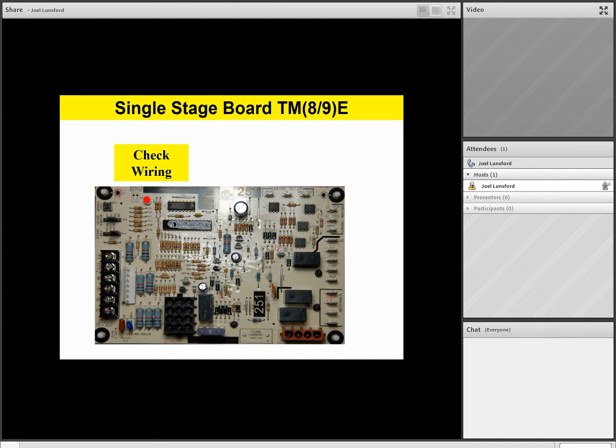In addition, did someone forget a jumper? As we said a few minutes ago, a technician sometimes will use jumpers for diagnostic purposes, which is okay, but we want to make sure that they don't leave the jumper on there, because what will happen, it will throw this flash code when you go into the heating mode again, because it'll think it's a stuck switch. So if no one forgot a jumper and it's not been rewired and so on, then if the switch is not opening after the call for heat goes away and the furnace shuts down, it should be open electrically. And if it's stuck closed, then at that point, please replace the switch.